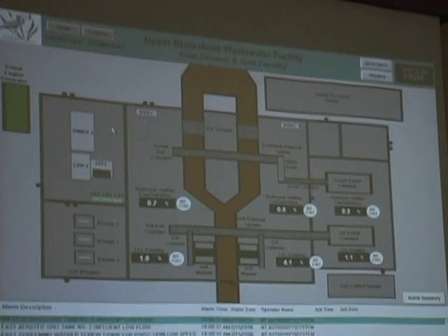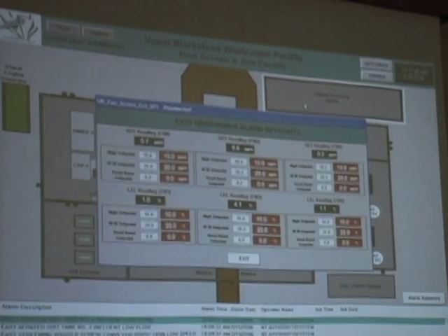information on things that you can't get locally or specifically deep down into the system. We have the H2S and the LEL readings here displayed because those kind of fit more with the overview of the system. And if you go into the set points area for this screen, you'll find that these are your LEL and H2S alarm set points that you're putting in.